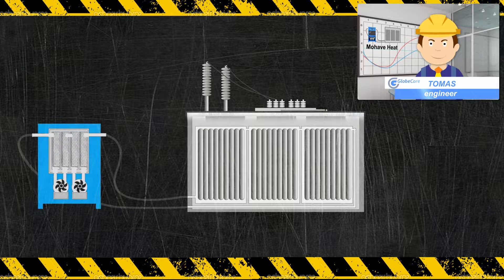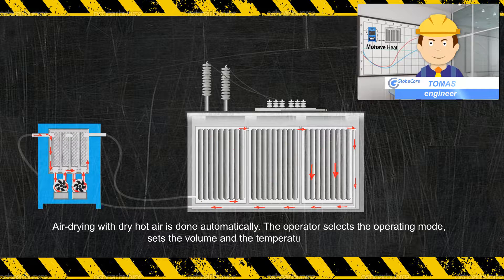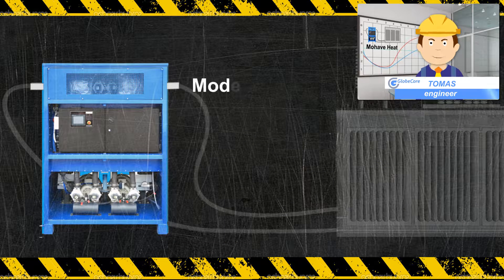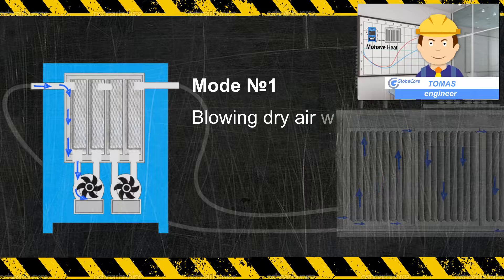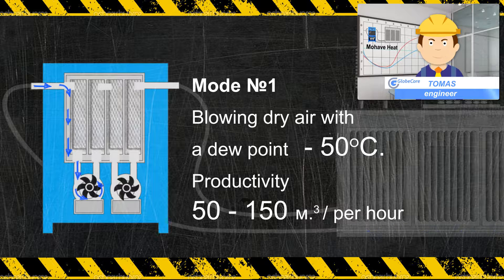The Mohave Heat Unit creates an excess pressure inside the transformer, thereby preventing the ingress of moist air. Mohave Heat dries the air to a dew point of minus 50 to minus 70 degrees Celsius and delivers it into the transformer, drying it in the process.